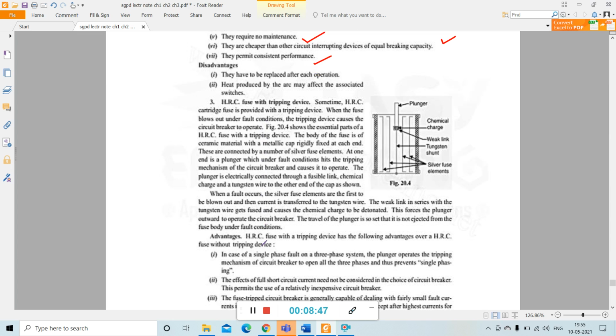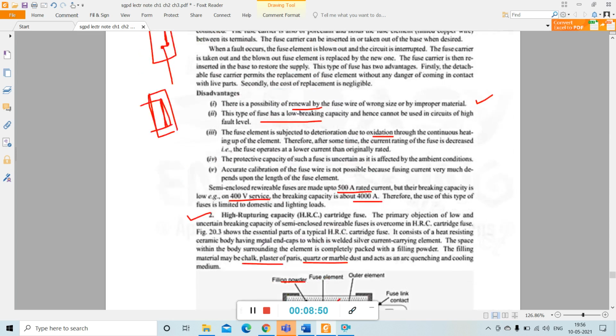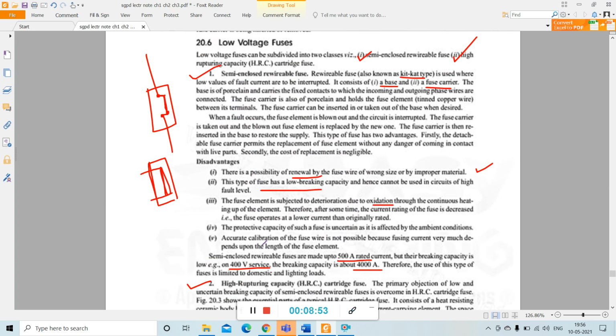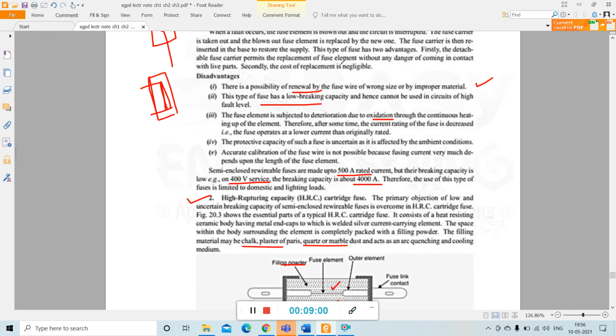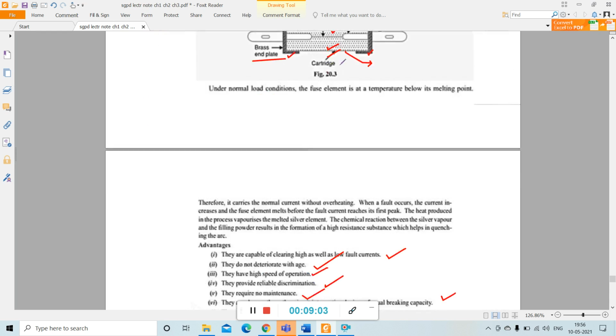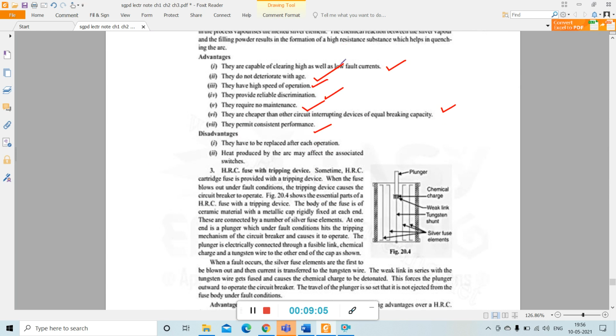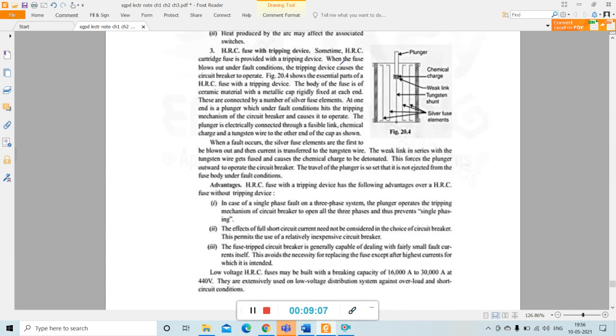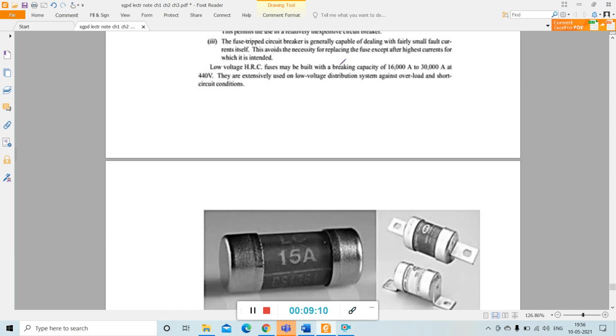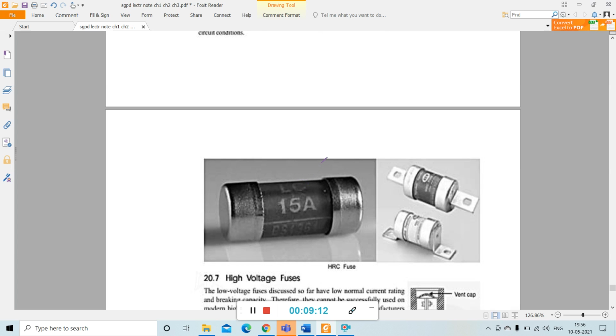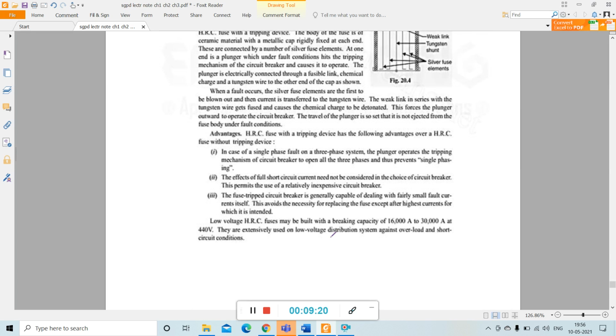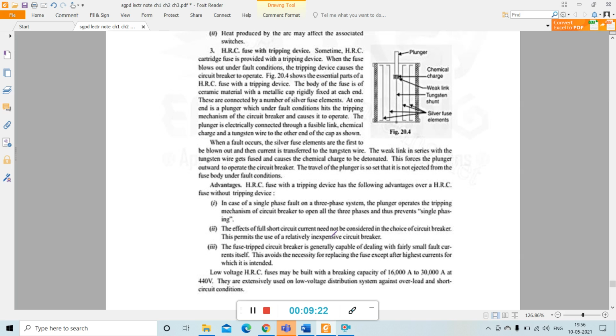And the third one is, as I told you in the sub classification, the semi-enclosed rewirable fuse and the high rupturing cartridge fuse. So the high rupturing cartridge fuse is one, and another type of HRC fuse is the HRC fuse with tripping device. These are the figures of cartridge fuses; cartridge fuses look like this. So see how the HRC fuse with tripping device operates.